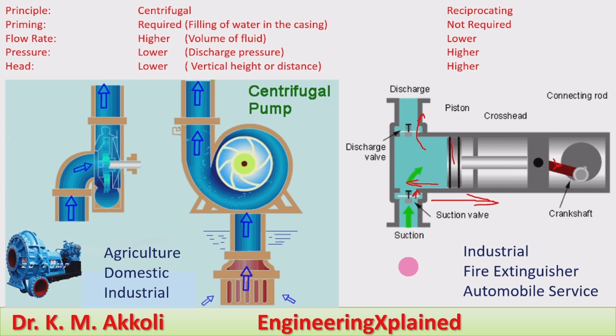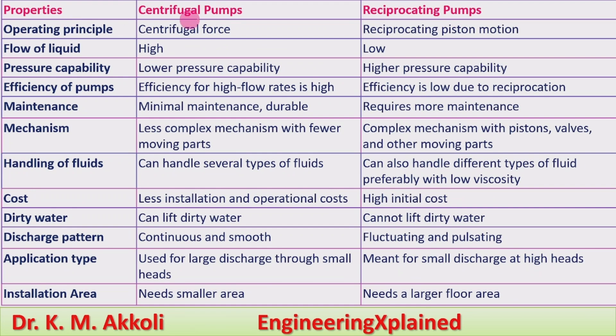Now we will take a list of other differences between the two pumps. Operating principle: centrifugal force versus reciprocating motion. Flow of liquid: high flow rate in centrifugal pumps, low flow rate in reciprocating pumps. Pressure capability: lower discharge pressure for centrifugal, higher discharge pressure for reciprocating. Efficiency: for high flow rates the centrifugal pump achieves higher output, so efficiency is higher for centrifugal and lower for reciprocating pumps.